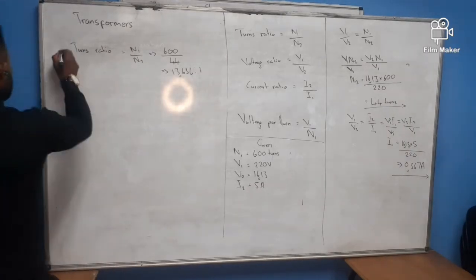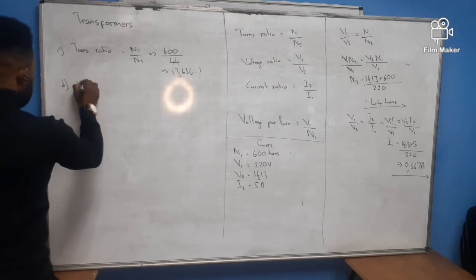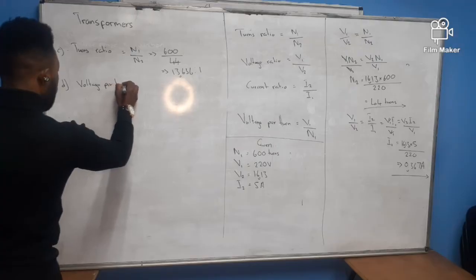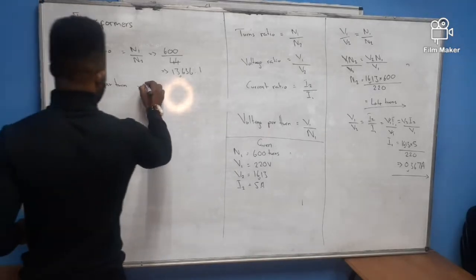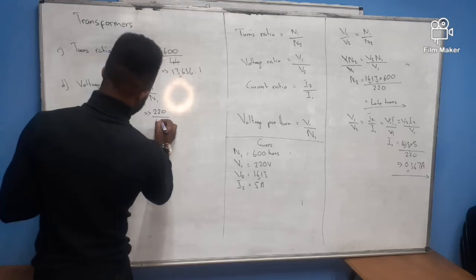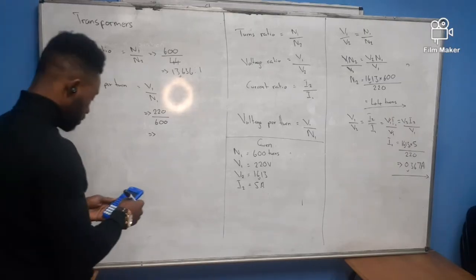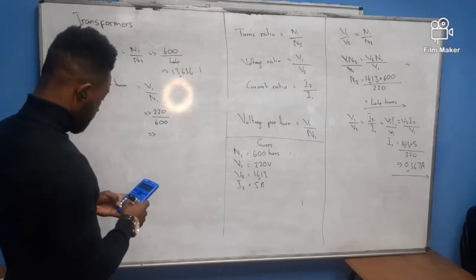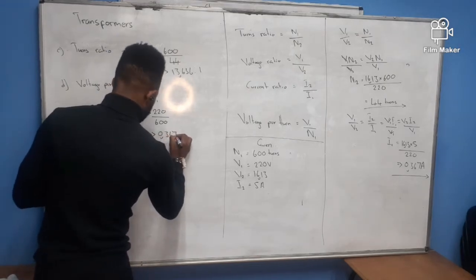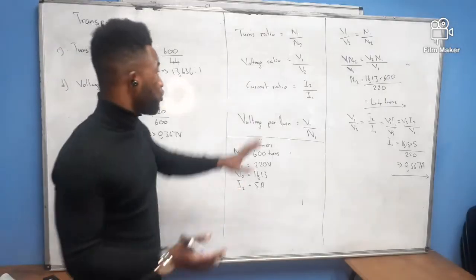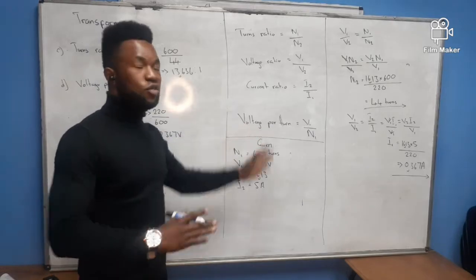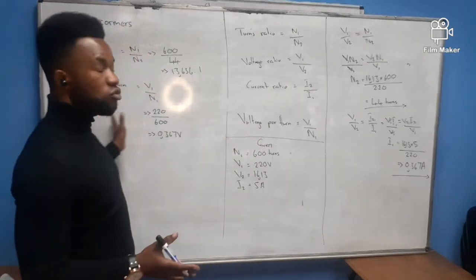Part D asks for the voltage per turn. The formula is V1 over N1: 220 divided by 600 gives 0.367 volts per turn. So, you just need to know your transformer equation and use it to calculate the turns ratio, voltage ratio, current ratio, and voltage per turn — the formula is also on your formula sheet.